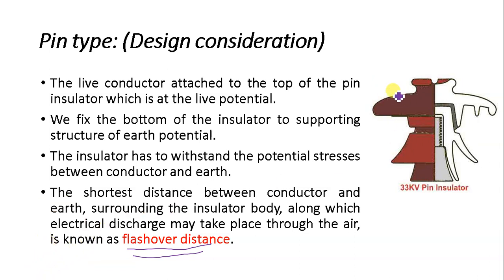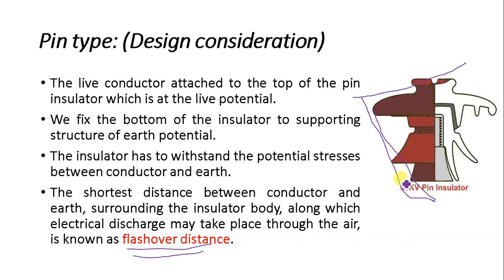When the insulator is wet, its outer surface becomes almost conducting. Hence the flash over distance is decreased because the wet, conducting part shortens the effective path. The design of the insulator must be such that the decrease in flash over distance when wet is minimized. The design consideration requires that the flash over distance should be as high as possible even under wet conditions.